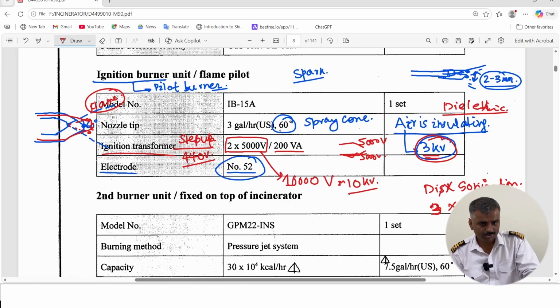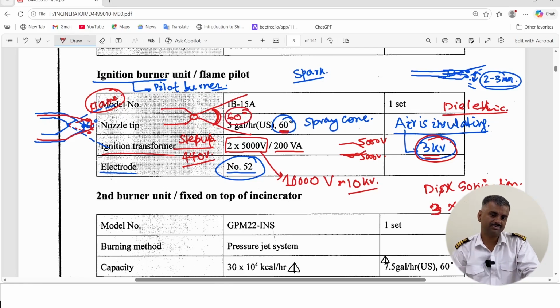And also the spray cone angle. If your nozzle is like this, the nozzle will spray the oil in the form of a cone, and the angle this cone forms is called the nozzle tip angle, or spray cone angle. You will have different spray cone angles for different nozzle tips. You can have 55 degrees, 60 degrees, 62 degrees. And 3 gallons per hour is the capacity.